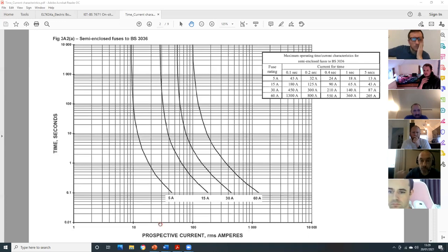28. Yeah, it's really up there, isn't it? It's getting close to the 30 amp line. I would say on this scale here, it's probably about there, so I would say 29 amps. And if you divide 29 by 15 amps, the device rating, you get a fusing factor of 1.9333, which is actually in the regs rounded up to 2.